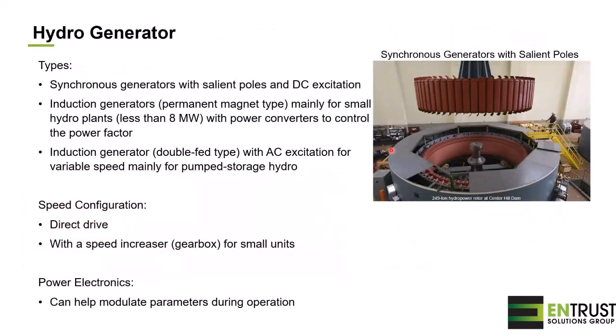Now on the generator side, there are different kinds of generators. The most popular one that we find in big projects mainly is a synchronous generator with salient poles. Here's an example of a salient pole. So all the poles are exposed on the surface of the rotor. We will have a north and a south, a north, a south, etc. And they are driven by a DC excitation. So there will be a DC exciter somewhere in the power plant, and from brushes, the current will go on the shaft, and from the shaft it will connect to the lead of a generator pole, and then all the poles will be connected together. So this excitation will provide a magnetic field to create the north and the south pole.